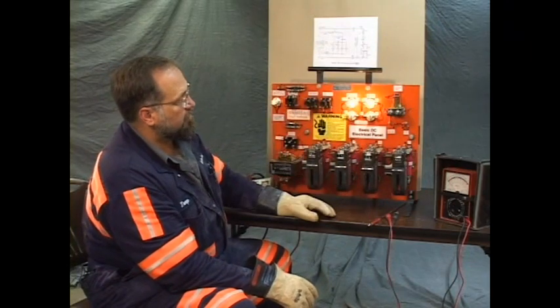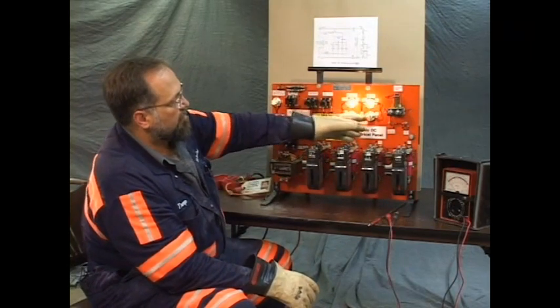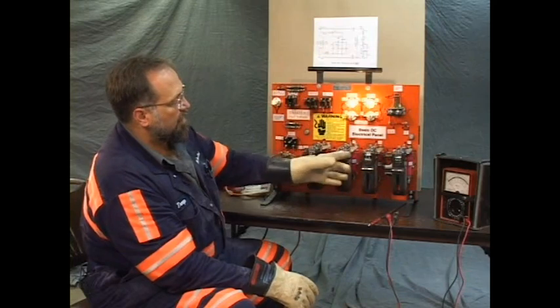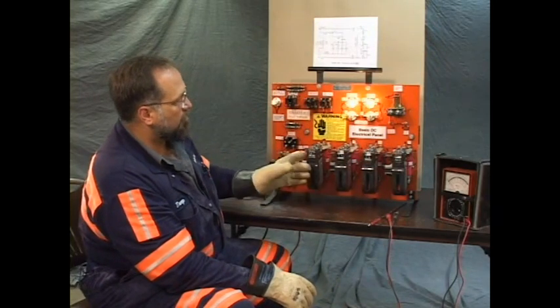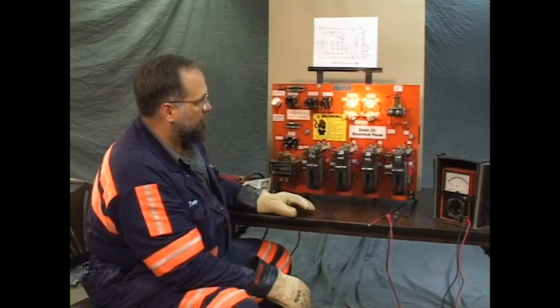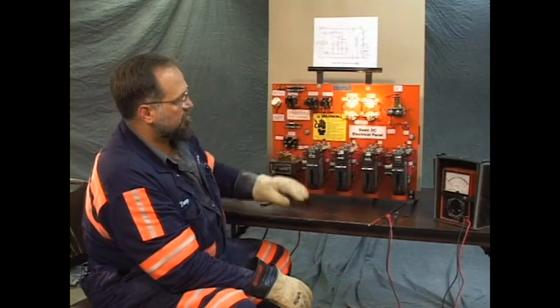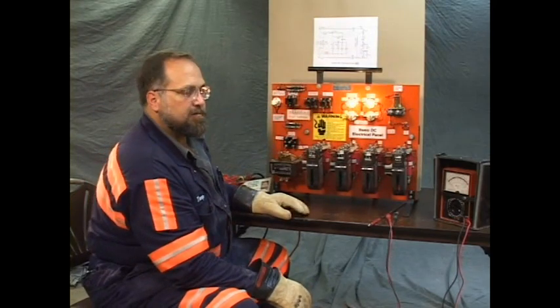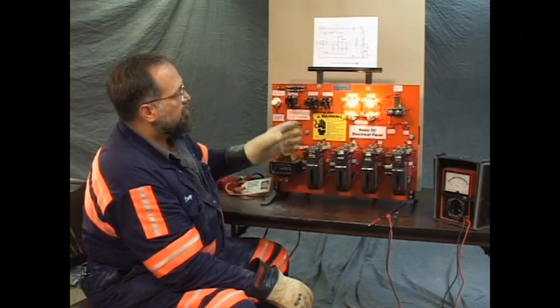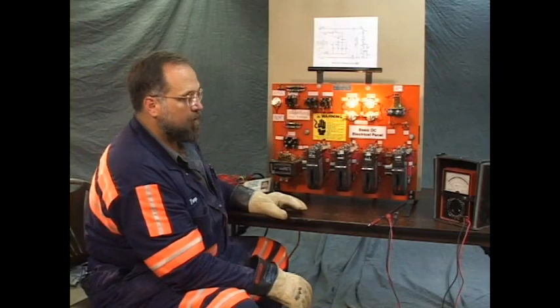When 2A closes, this light goes off. It's bypassed. It goes through the contactor, goes around the resistance rather than through it. The effect of that is the armature light shares its power with nothing. It's as bright as the shunt field. The motor's at full speed.